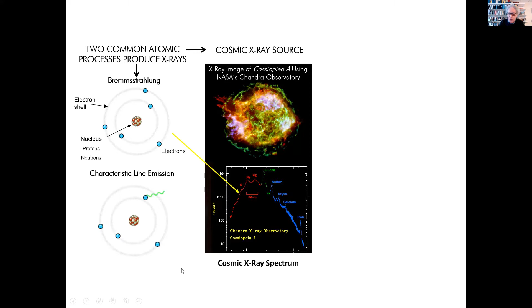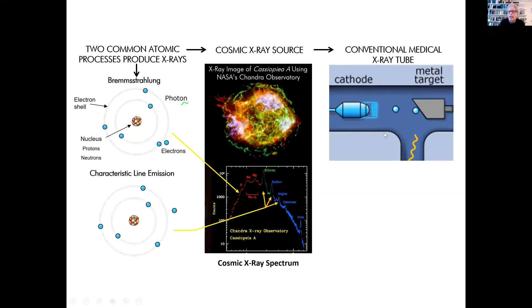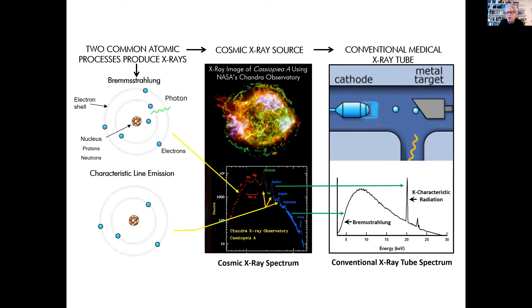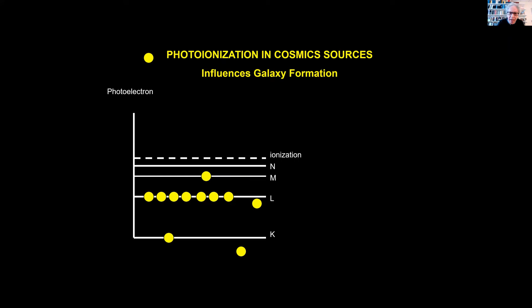And so now let's move to a terrestrial source, which is the conventional medical X-ray tube. You've got the cathode emitting electrons bombarding a metal target, and it makes the continuous spectrum, which is analogous to what comes from a celestial source, with some characteristic line radiation on top. But we also use an additional process that takes place in the universe, called X-ray fluorescence, which in a cosmic source is a photoionization. You can excite an atom by irradiating it with an X-ray photon. You can make, therefore, a photoelectron. You then have a vacancy in the K shell, which is filled by an electron from an outer shell. Each one of these two photons is monochromatic because of the quantized nature of the atom, and every atom has a characteristic X-ray based on its atomic structure.